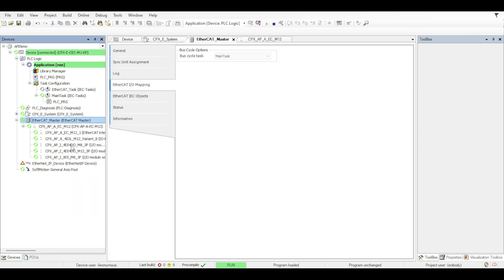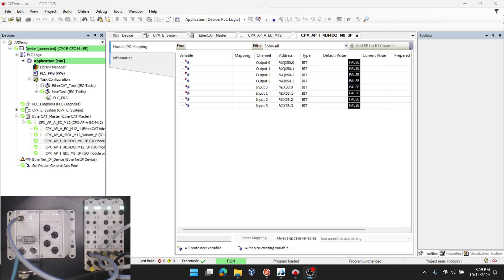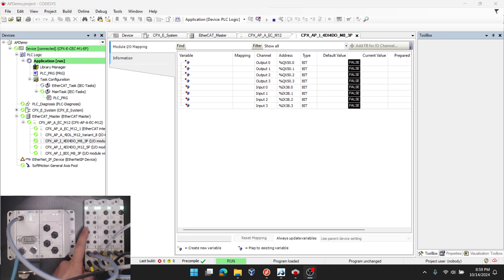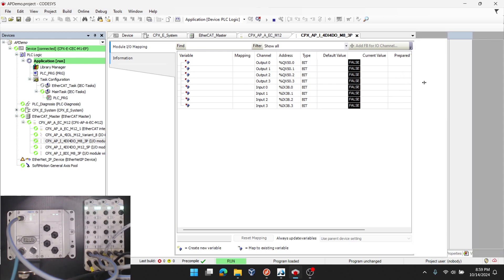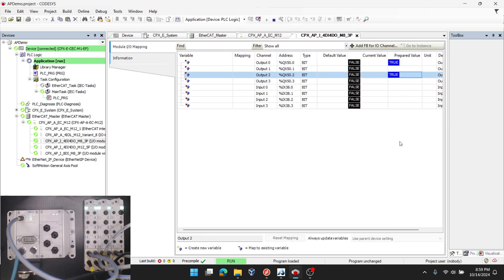Now I'm going to minimize the CPXE system and open the settings for my 4DI 4DO module, the first one. By double click on that slice, you can see I can verify the current status of that module. You can see here on the very left side, there's all these LEDs next to each port that indicate if they're off or on and all of them are currently false or off. By going to the prepared value column, you can see I can come to digital output 0, 1, 2, and 3 for that slice, and I can prepare different values for each.